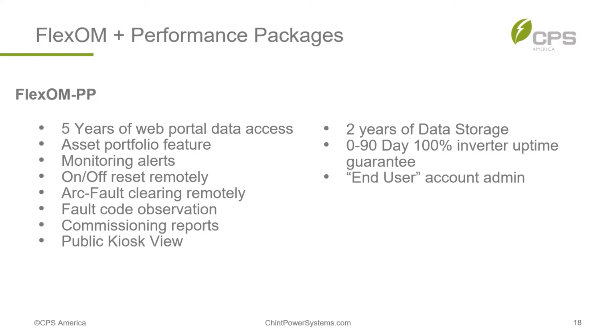Some additional features of the FlexOM portal are configurable monitoring alerts, ability to turn inverters on and off remotely, clear an arc fault remotely, set active power factor, clear a fault, configure and download site commissioning reports, and access a customizable public kiosk that can be used to display production data in the lobby of a building to showcase the PV system.